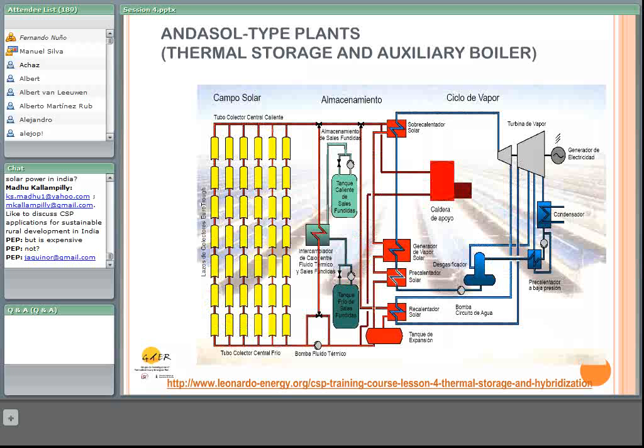In the case of parabolic trough plants with thermal oil as heat transfer fluid and thermal storage, like many of the plants in Spain, for example the Andasol plant, the auxiliary boiler is placed on the oil side. This is due to different reasons. First of all, according to the Spanish regulation, the natural gas burner must be placed on the side of the heat transfer fluid.